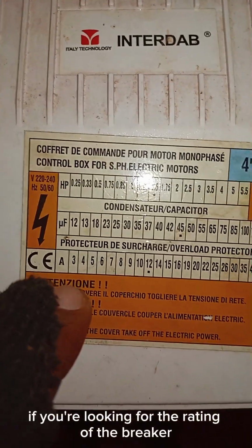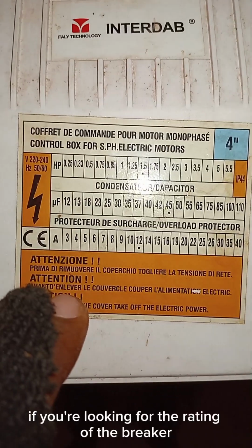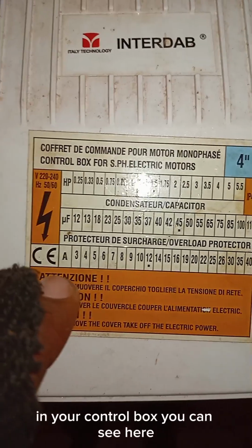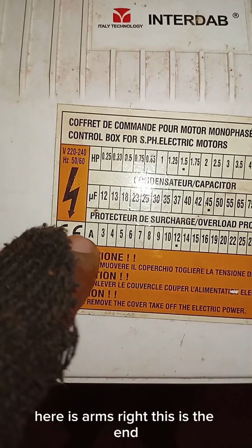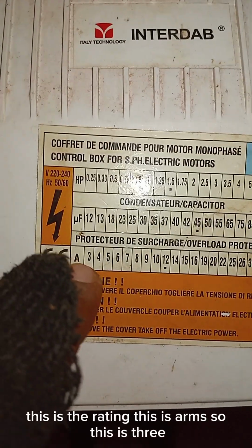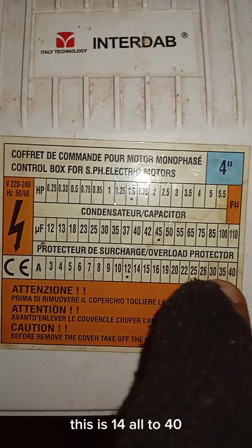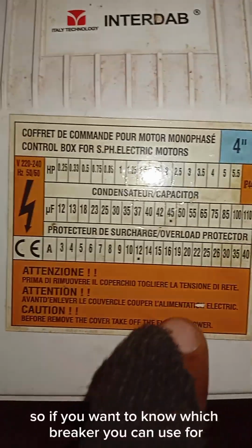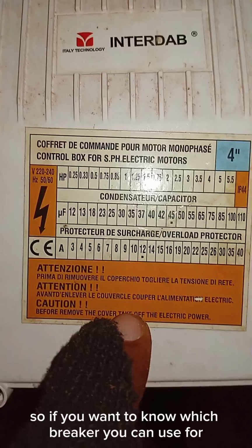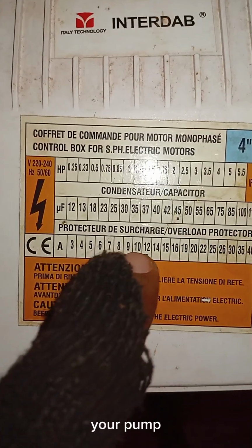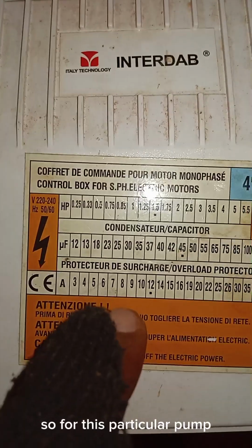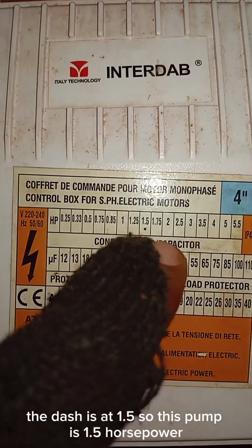If you're looking for the rating of the breaker in your control box, you can see here it is in amps. This is the rating, these amps. So this is 3, this is 4, this is 15, this is 12, this is 14, all to 40. If you want to know which breaker you can use for your pump, you check where the dash is under the number. For this particular pump, the dash is at 1.5.